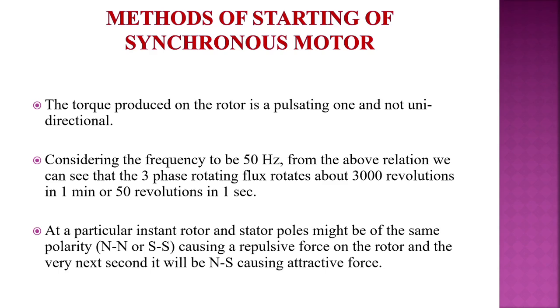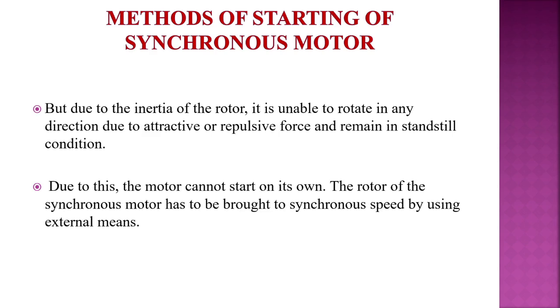So already we have seen the reason for the synchronous motor being a non-self-starting machine: at a particular instant the stator and rotor poles can be of the same polarity, and in the next moment they will have opposite polarity. Same polarity causes a repulsive force and opposite polarity causes an attractive force. Due to the inertia of the rotor, it is unable to rotate in any direction due to the attractive or repulsive force, and it will remain in the standstill condition. The attractive and repulsive forces cancel each other.